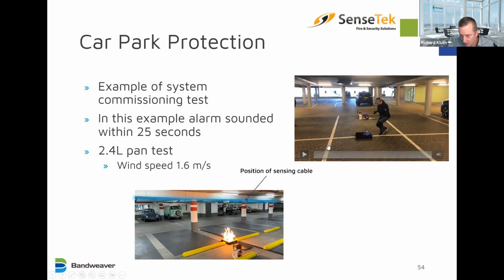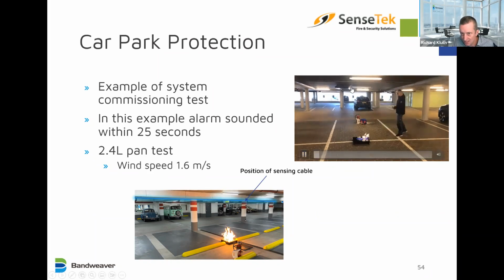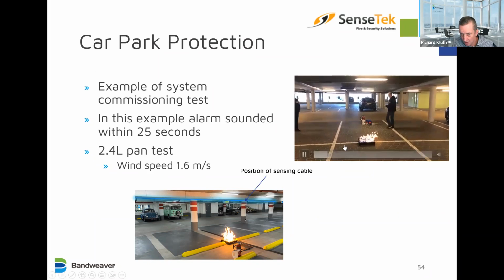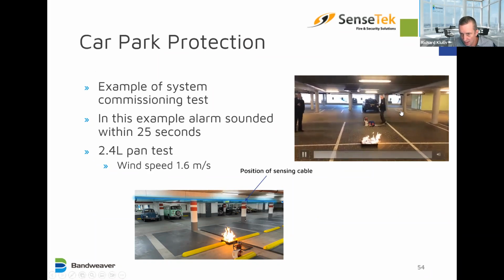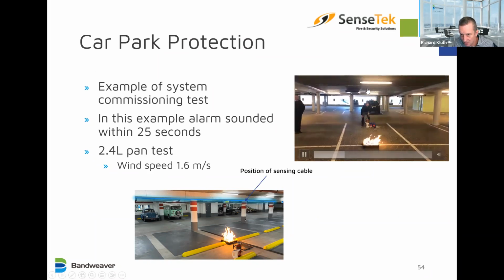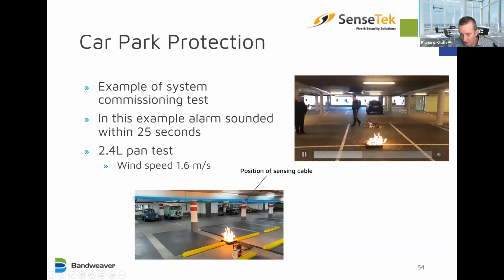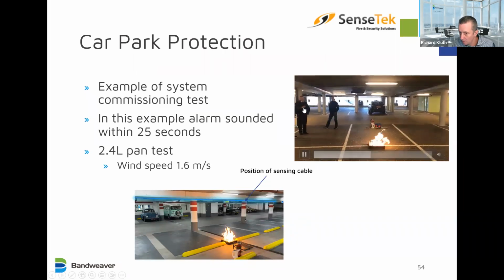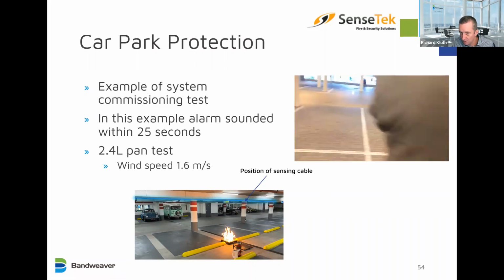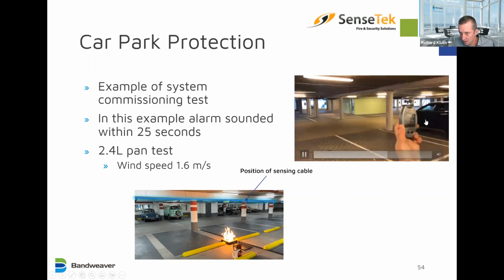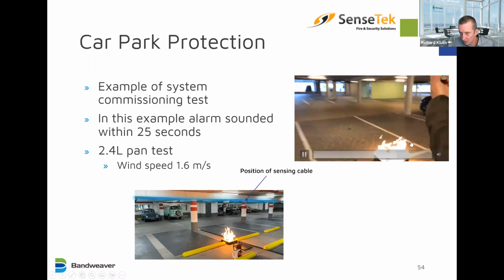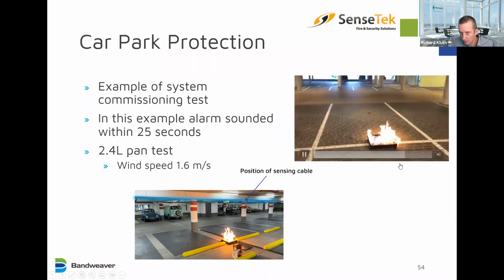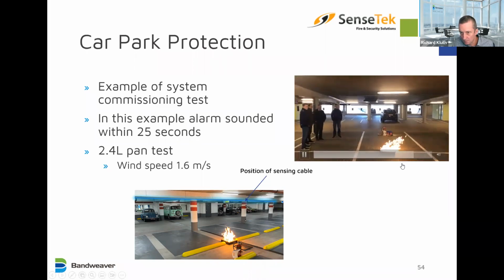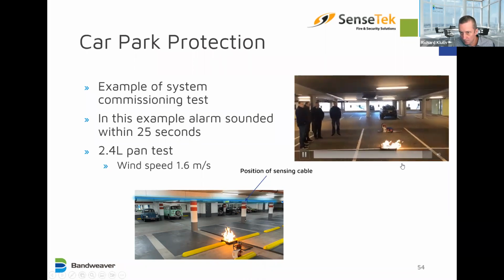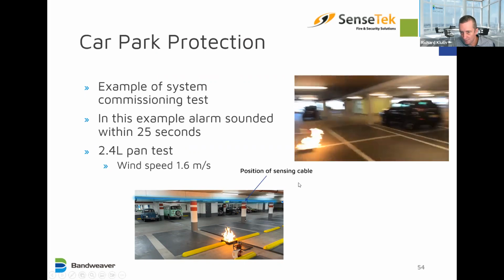In the video here, we'll see our colleague at SenseTek, who installed that, lighting the fire pan test and walking away to an area of safety. The cable is here at this point. He's now joining the colleagues from the Netherlands Fire Department. You can see the wind speed is 1.6 meters per second, and you can hear the alarm going at that point after 25 seconds.